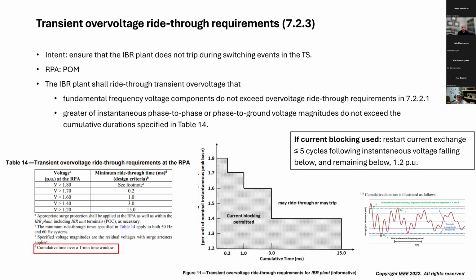But assuming that we're still in a ride through mode of operation or a continuous mode of operation for our phasor domain voltages, the requirement here is that the instantaneous phase to phase or phase to ground magnitudes do not exceed these thresholds in Table 14 for this time duration in the next column. Pictorially, it looks like this chart here in Figure 11. A couple of key notes: this is cumulative over a 1 minute window, and there's a footnote in the standard that gives an illustration of what that looks like. You're going to have the thresholds on both the positive and negative side of the waveform. So anytime it goes over the threshold, you can add that time up to see if you're in a must ride through, or if you're in a may ride through or may trip area.